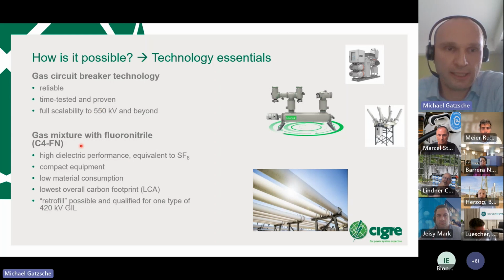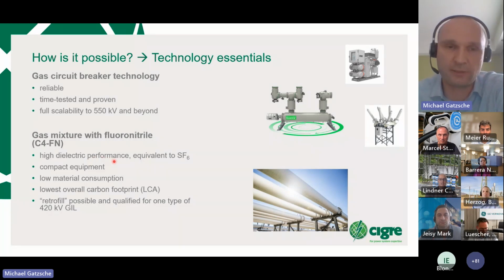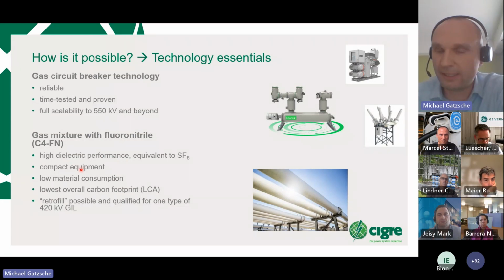The other factor is the gas mixture with fluoronitrile. So why do we need it? When moving away from SF6 to SF6 alternatives, the C4 additive is the only option to achieve high dielectric performance comparable to SF6, and this high dielectric performance enables compact equipment. If we leave out the C4, the dielectric performance drops and the size increases.